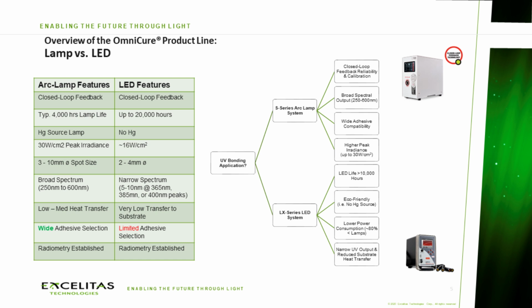For the LED-based system, the LX series, that system has a typical LED life of greater than 10,000 hours. Of course, in that system you're using LEDs, so there's no mercury source, no lamp, and the power consumption is typically considerably lower. The other thing that differentiates it from the lamp-based system is that LEDs, for the LX series, are pretty much single wavelength, whereas the lamp-based system is a very broadband source.